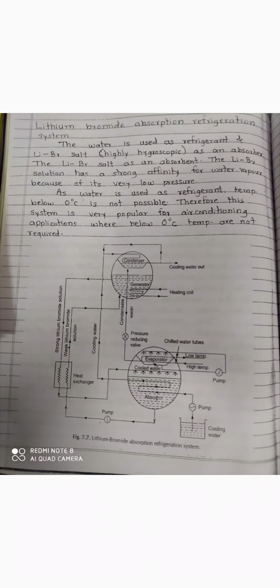Now see the working of this system. We'll start from the evaporator. In the evaporator, water evaporates by absorbing heat from the water and lowers its temperature to 2 degrees Celsius. This cold water is used to cool the water that is used for the conditioning purpose. As the water evaporates in the evaporator, that vapor is absorbed by lithium bromide in the absorber, and that solution becomes a weak solution.